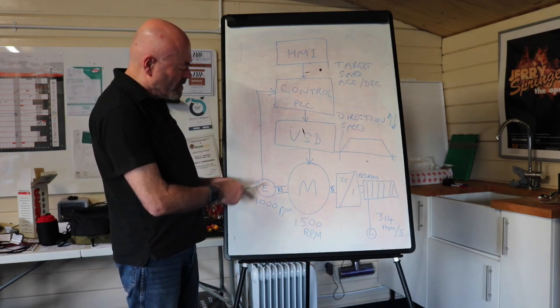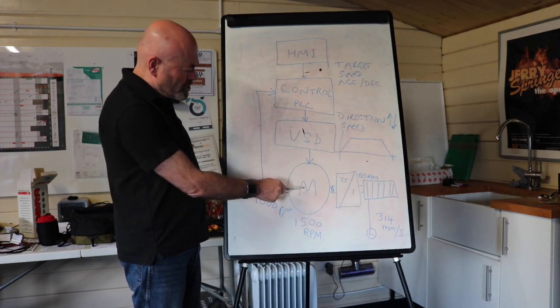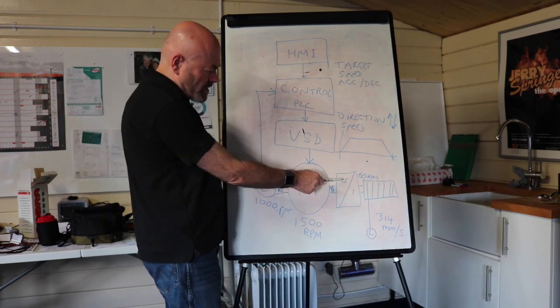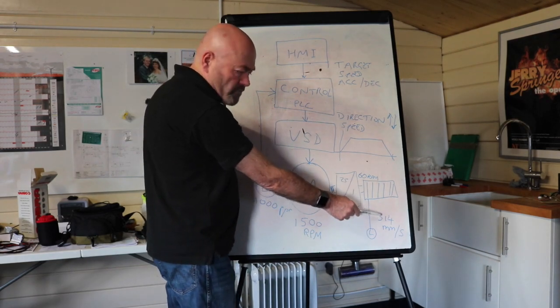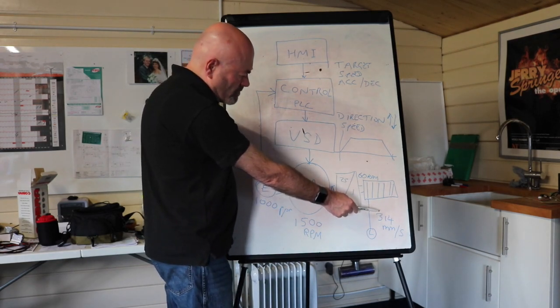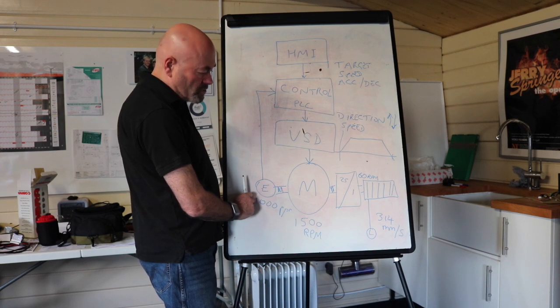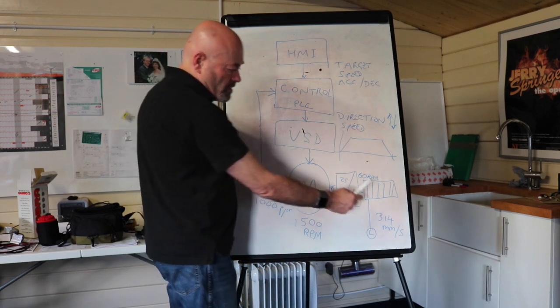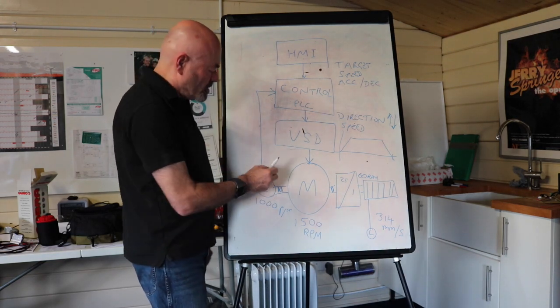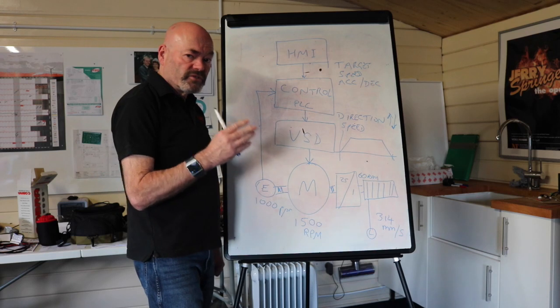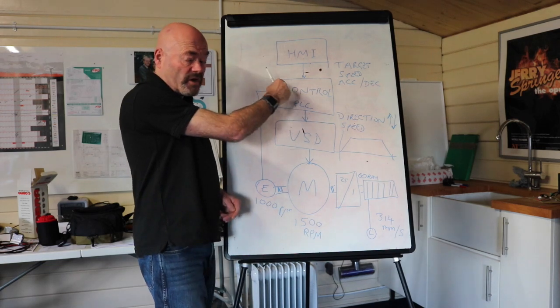Also, we can scale it. If we know there's a thousand pulses coming out here for one revolution, and we know we're turning down 25 to one, and we know the diameter of this drum, we know that at full speed we're going to do 25,000 pulses, and we know this is going to do 314 millimetres. So 314 divided by 25,000 gives us a scaling factor so that we know not only how fast it's going, but we also know how far it's travelling.